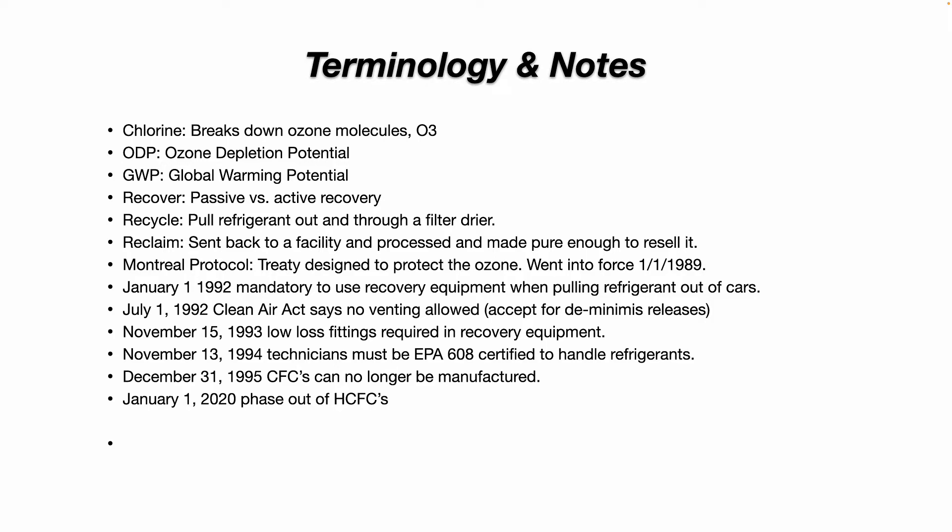Three other important terms you'll see on the exam: recover, recycle, and reclaim. When you recover refrigerant, you pull it out of a piece of equipment into a recovery cylinder, then make a repair and put the refrigerant back. When you recycle refrigerant — common in the automotive space — you pull the refrigerant out, run it through a series of inline filter dryers, and then put it back in that equipment.